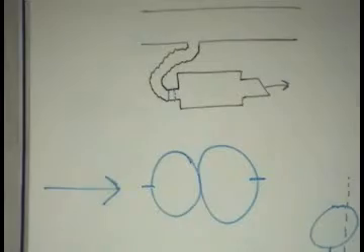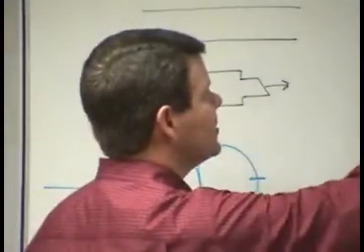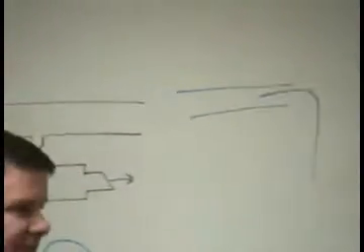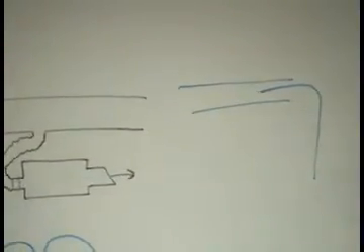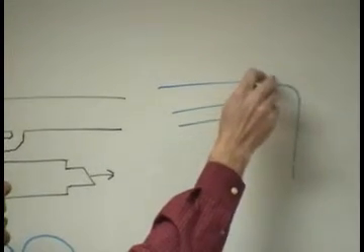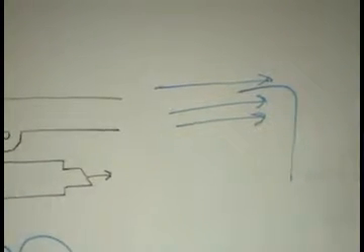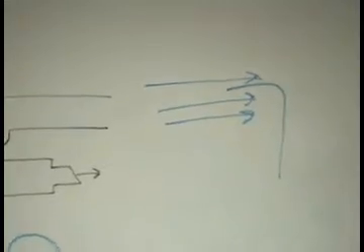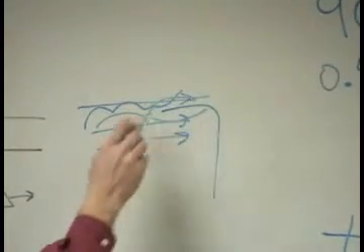Because when I've got my pitot tube here, I've got to get some straight air, like the nice picture that I gave you in the handout here. We can have nice laminar flow. That thing can read and give us a pretty accurate reading. If this air is swirling around when it goes by there, that differential pressure is going to be whacked and it's not going to be accurate.